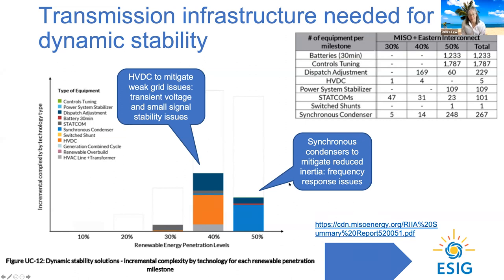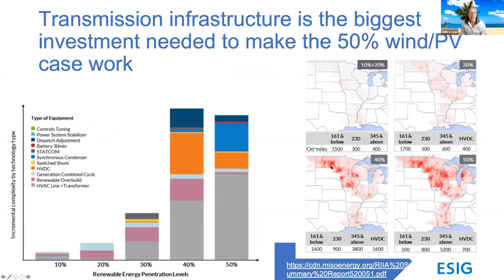Then when they got to the 50% penetration level, they ran into a different kind of issue. The system had low inertia and they were running into frequency response issues and had to install a bunch of synchronous condensers to help mitigate that. So when you add up all the different things that they did, and that's what this graphic shows for all the different aspects of their studies, you'll note that a huge amount of what they do to make the system work at the 50% level is AC transmission, DC transmission, and FACTS devices, basically transmission infrastructure. There are other little things like a little bit of combined cycle and a little bit of renewables overbuild, but the vast majority of solutions and infrastructure needed was transmission.